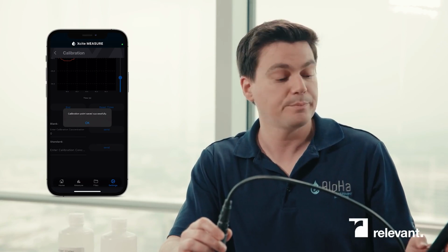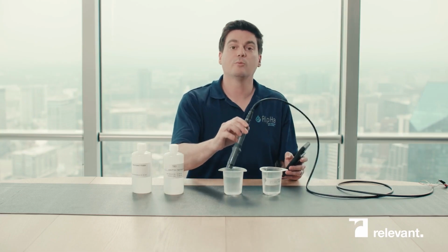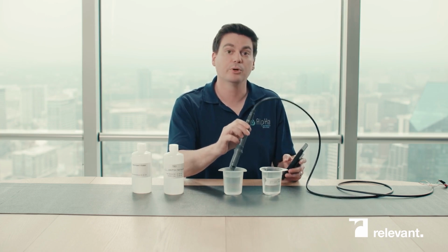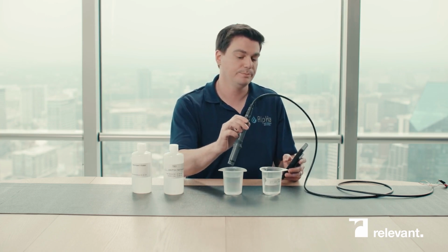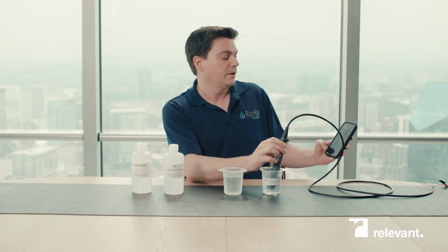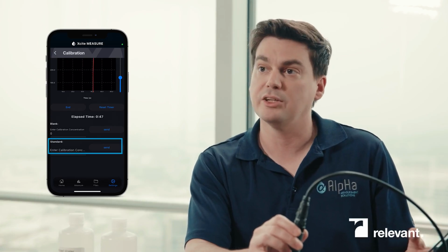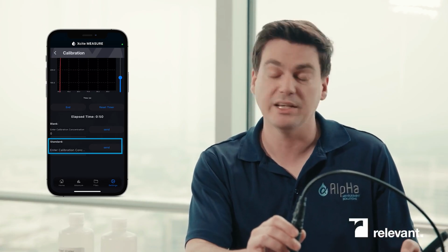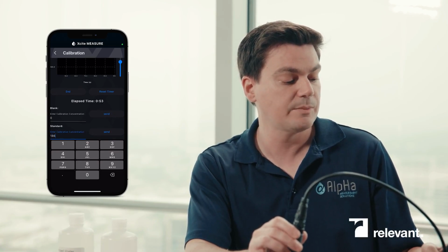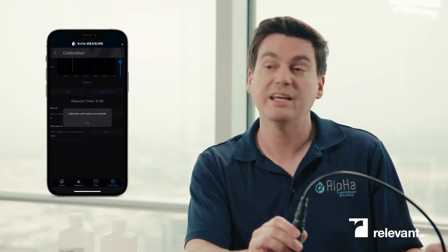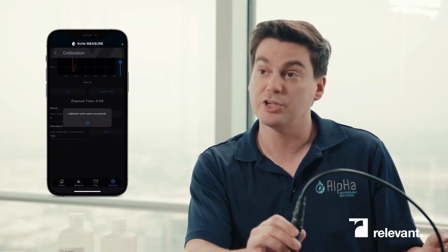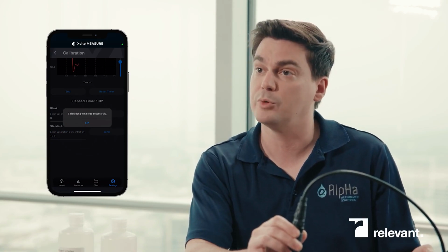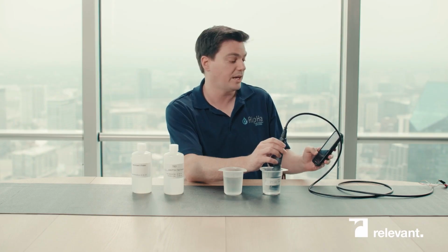Once the calibration is successful, a notification will pop up on the screen: Calibration point saved successfully. You'll hit OK. And then you'll do your 2-point calibration. So the first point is done. Now you'll put it in the 186 solution right over here. On the screen itself, there's what's known as the standard. The standard is going to be your second point that you do, and in this case, as we said, it is 186. So simply type 186 into the device and then hit send. Once you hit send, just like on the blank, it will pop up that the calibration was saved successfully. Hit OK to get back to the main menu.